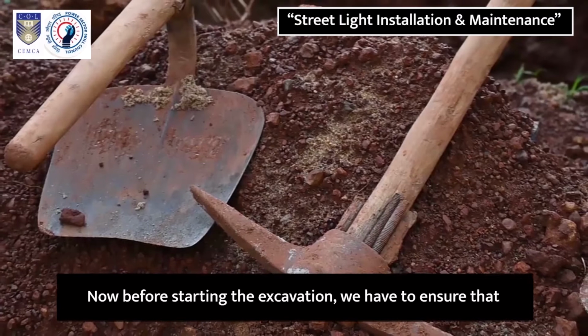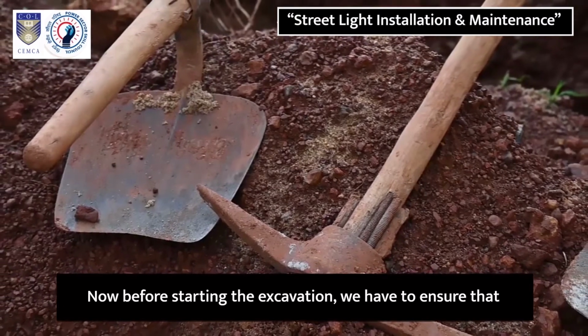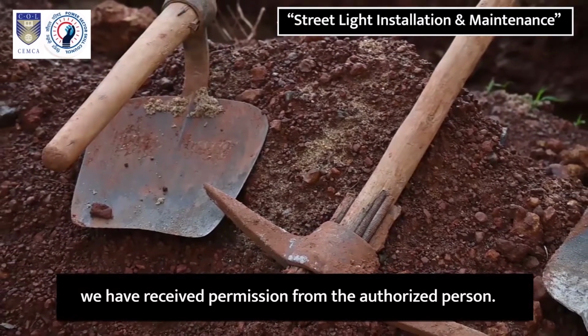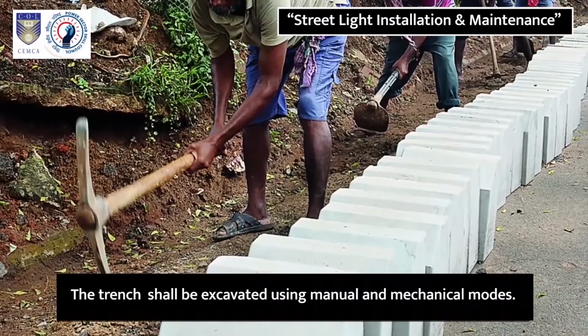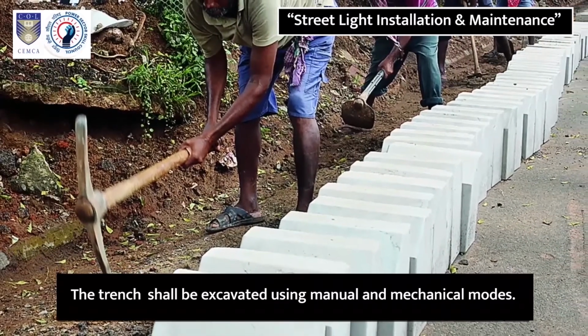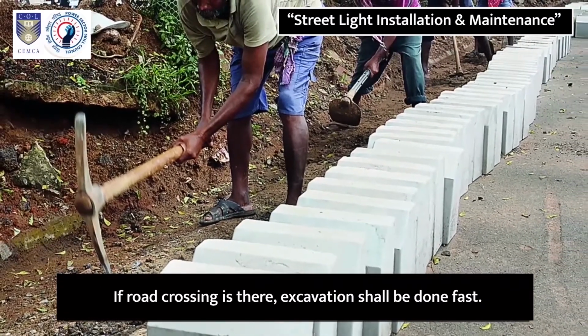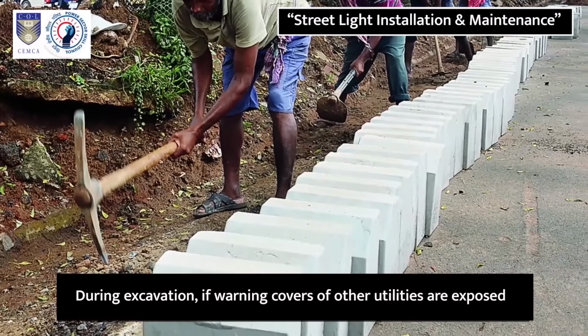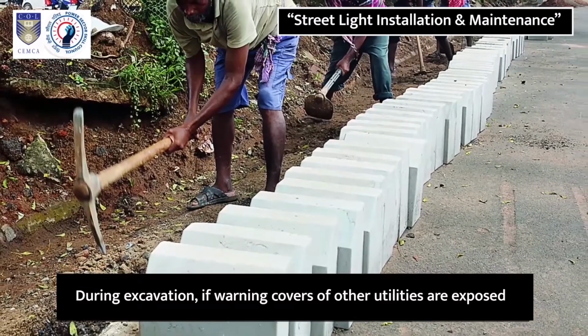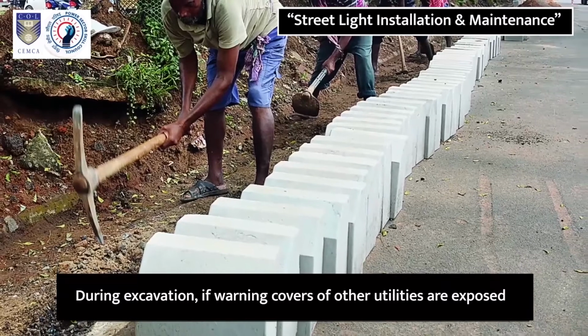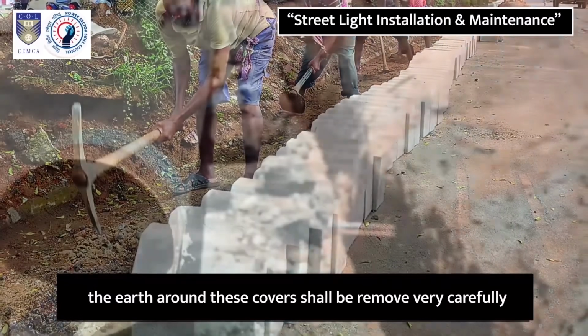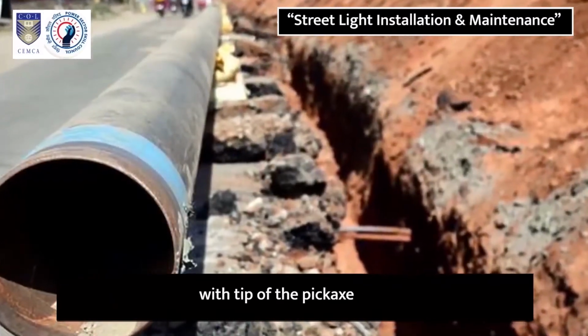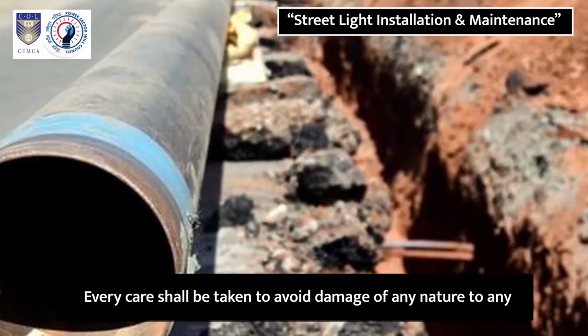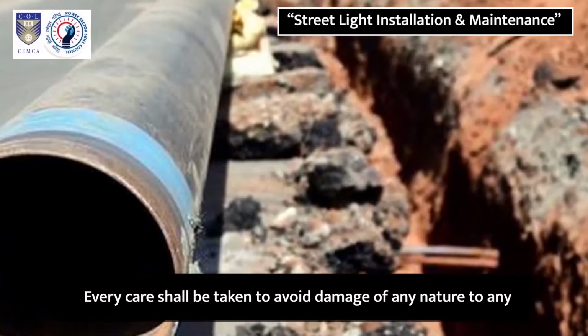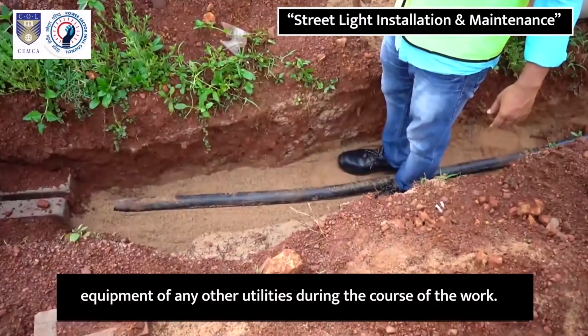Now, before starting the excavation, we have to ensure that we have received permission from the authorized person. The trench shall be excavated using manual and mechanical modes. If road crossing is there, excavation shall be done fast. During excavation, if warning covers of other utilities are exposed, the earth around these covers shall be removed very carefully with tip of the pickaxe.